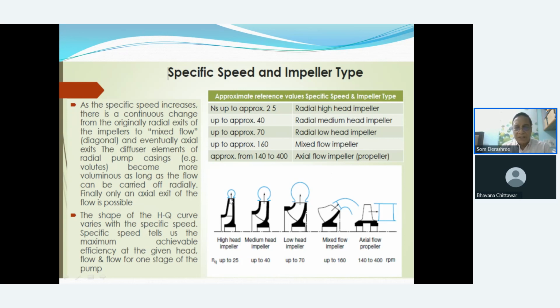It starts as a very steep radial, then gradually moves towards the horizontal axis. It comes to a mixed flow, where it's radial plus axial, and then you have absolute axial. So specific speed is a dimensionless entity which you have to find out at the design stage. Then you know what kind of curve you're fitting in, and accordingly you ask the supplier or manufacturer for an axial propeller type, or a mixed kind of flow. They'll give you basic guidelines on that.